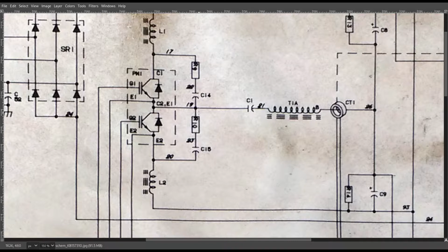The area I'm looking at for these tests is near these IGBT modules. I'm looking at the gate drive signals, so gate to emitter - if I disconnect this temporarily, gate to emitter should be an open circuit. This is an insulated gate, that's why they're called IGBTs, and there's not supposed to be any contact there. Same thing between this gate and this emitter.